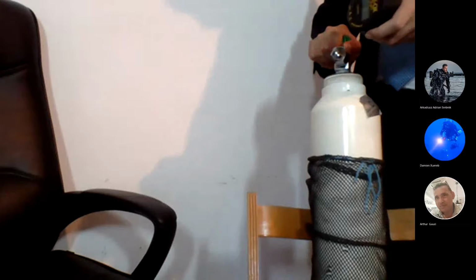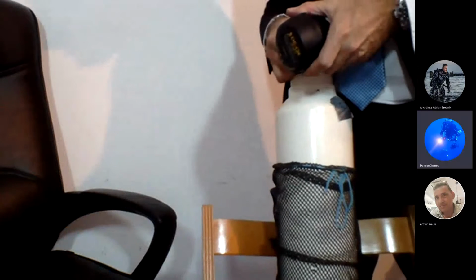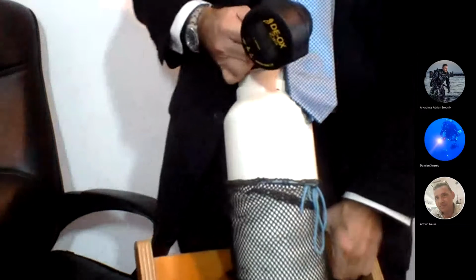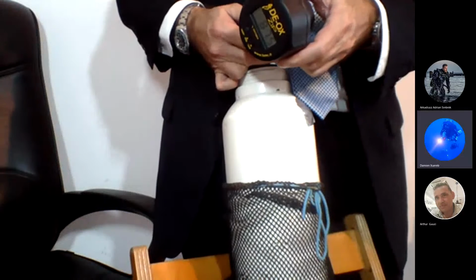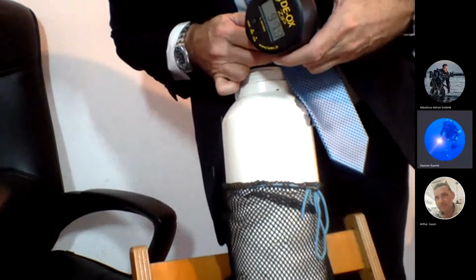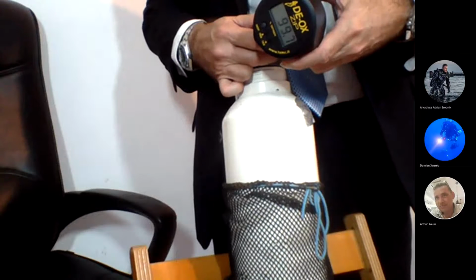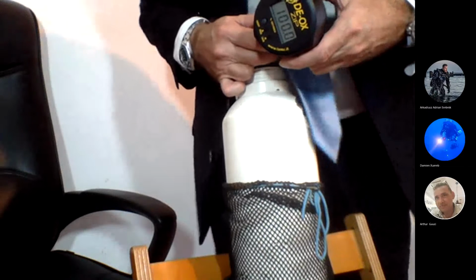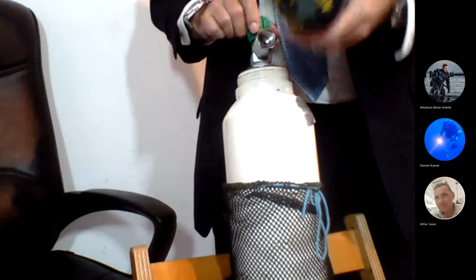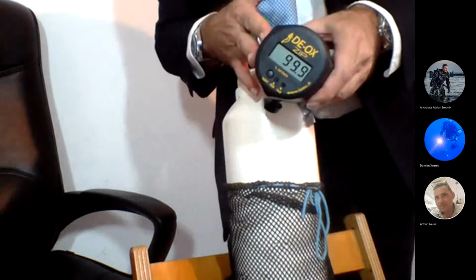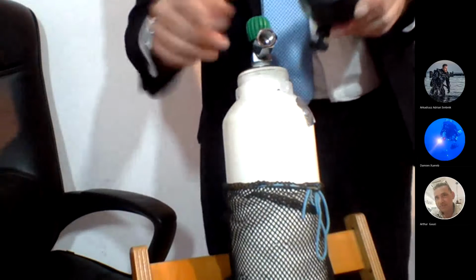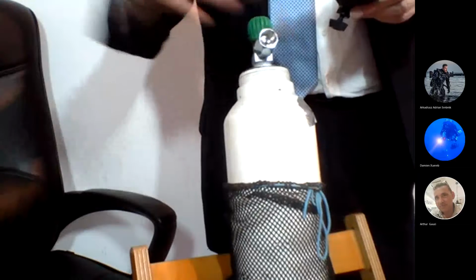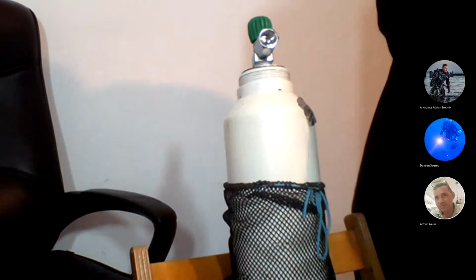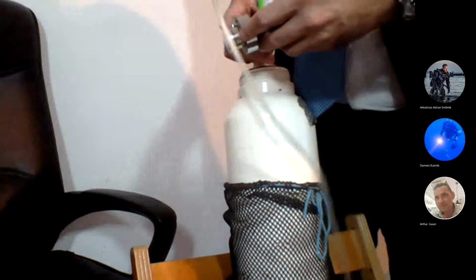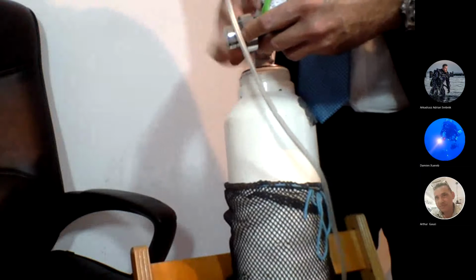Let's do it the different way. Can you see the display, guys? How much is it showing? 98, 99, no? 100? Okay, that's good. So as you can see, the sensor was well calibrated, and now it's giving good accuracy even with pure oxygen, even though we are very far from the 21% where we did the calibration.